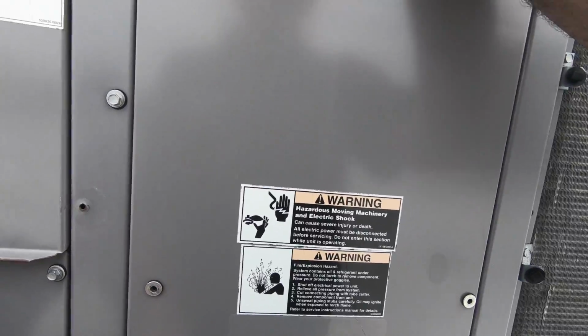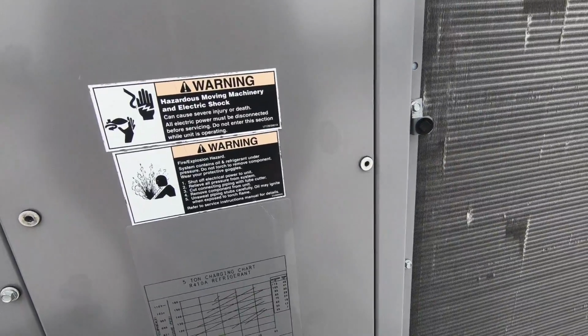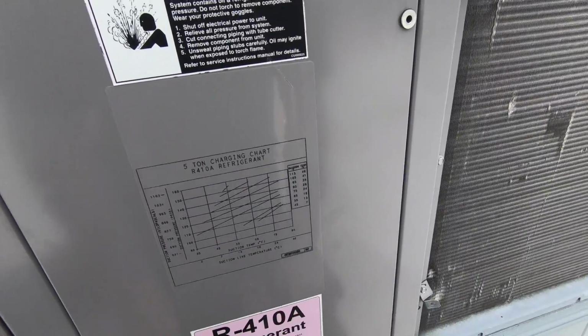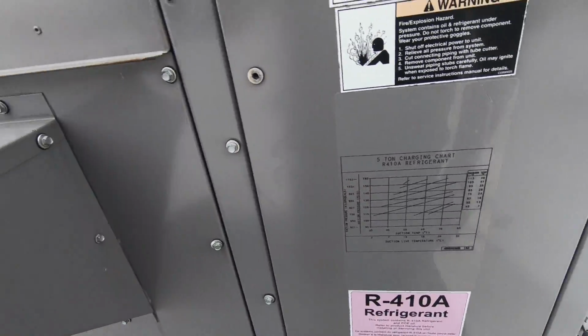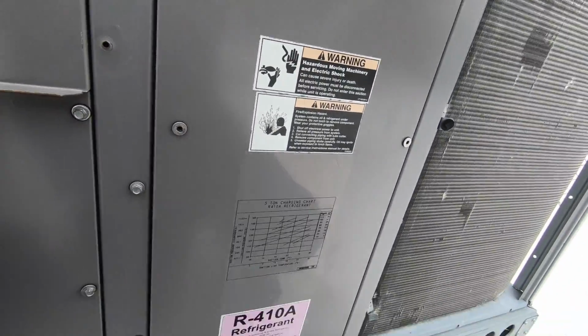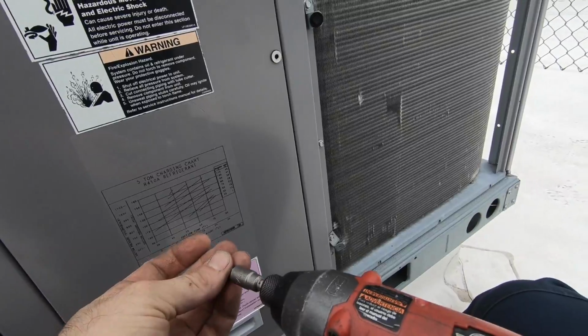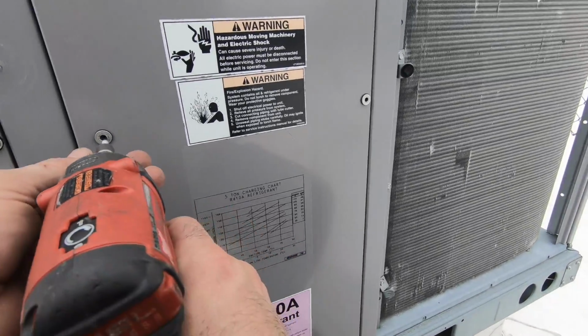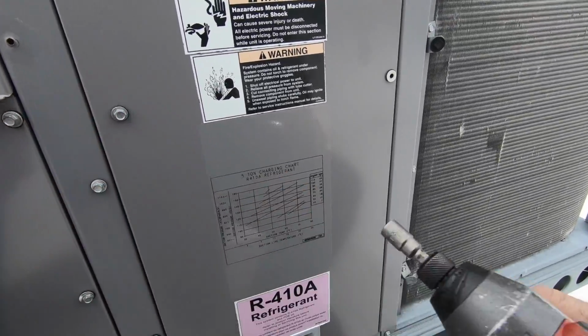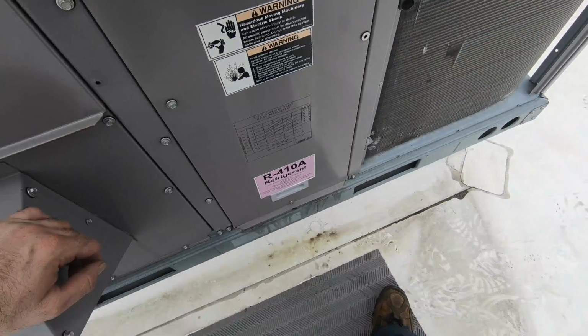I more or less want to see what my superheat is here, because of the humidity issue, my coil may not be getting cold enough. Also what my temperature split is. Also how humid is my return air, because my return air is very humid. There's only so much this unit's going to be able to do. And I'm around on this side.